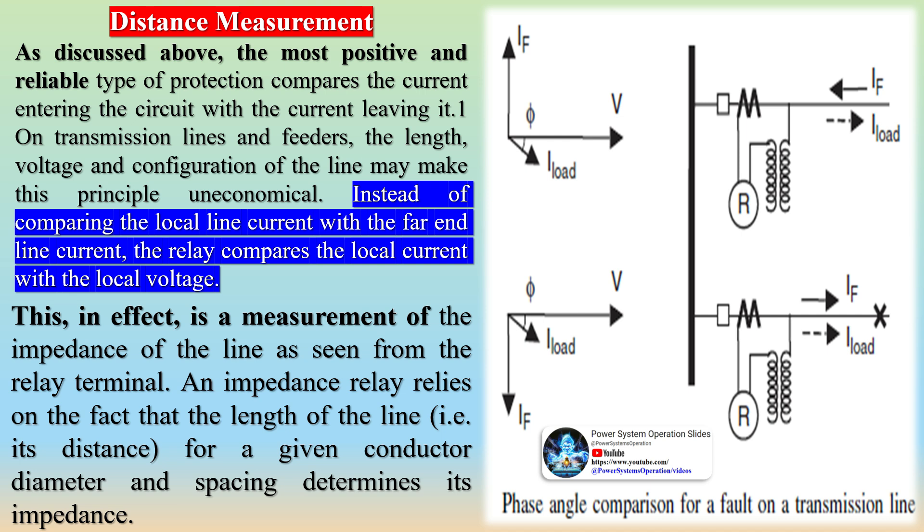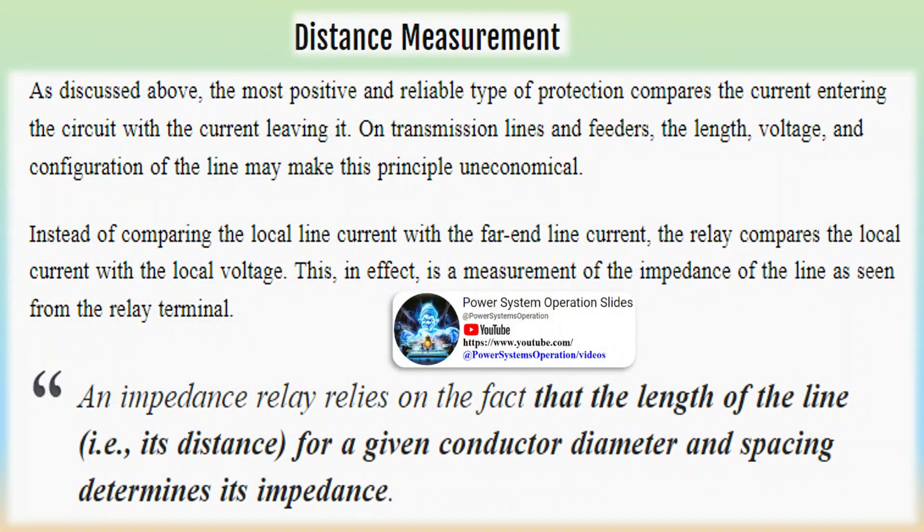Distance measurement. As discussed above, the most positive and reliable type of protection compares the current entering the circuit with the current leaving it. On transmission lines and feeders, the length, voltage, and configuration of the line may make this principle uneconomical.